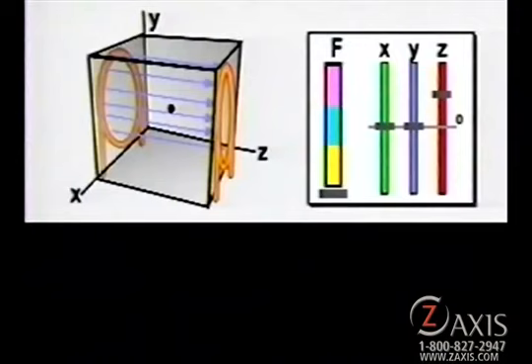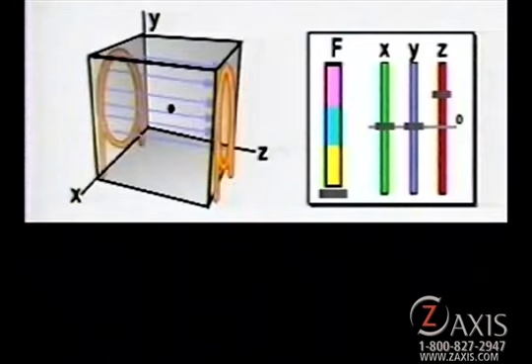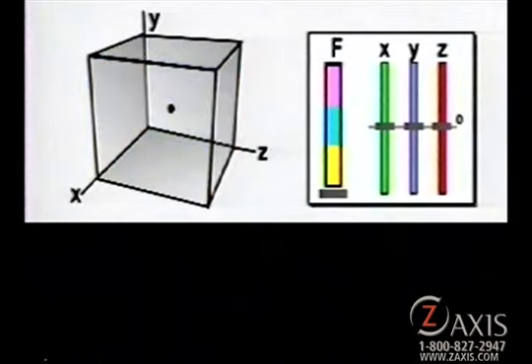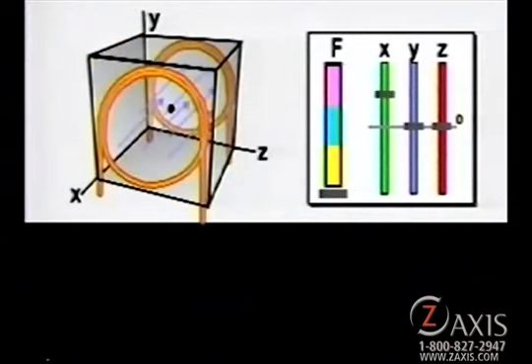This exhibit shows the location of those coils on the left side of the screen and the coil controls in the box on the right. The green, blue, and red bars labeled X, Y, and Z are slider-type controls that represent the electrical power applied to each coil. For example, when the Z slider is pushed up from its neutral or off position, the Z coils are energized and produce a magnetic field indicated by the purple arrows inside the scanning volume. The other coils work in the same fashion, producing their magnetic fields in the other two directions.